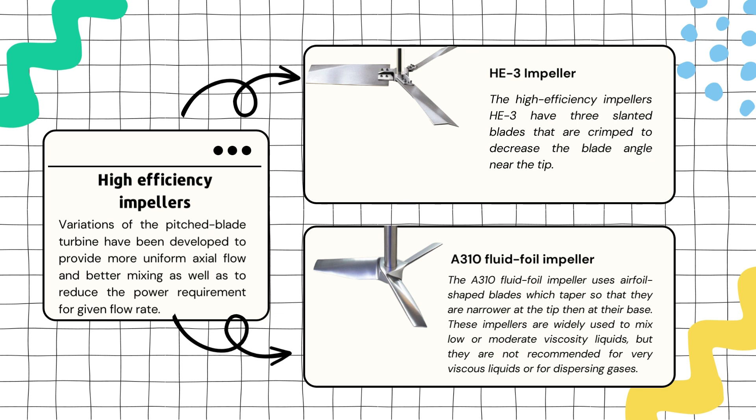One example of a high efficiency impeller is the HE3 impeller, which has three slanted blades designed to decrease the blade angle near the tip. This design ensures more uniform axial flow and better mixing. Another example is the A310 fluid foil impeller, which uses airfoil-shaped blades that taper, making them narrower at the tip than at their base.